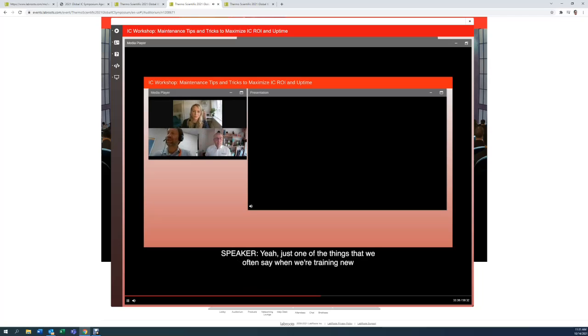One of the things we often say when training new users is to make sure, as Andrew said, maybe a minimum of weekly. We encourage people to have a routine, maybe on a Monday morning, regardless of what's happened with the system, even if it's used intermittently. Any water for the eluent, or even the wash bottle for the autosampler, should be replaced at a certain time of the week. The bottles all get rinsed out and replaced once a week, so it never ends up sitting there for too long. That routine helps to stop that sort of thing from happening.